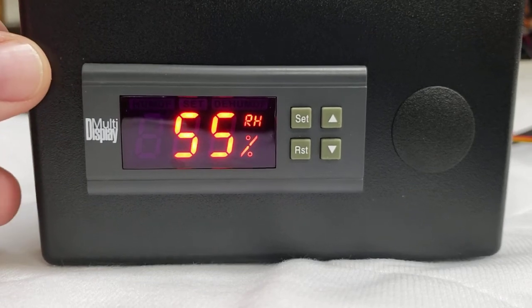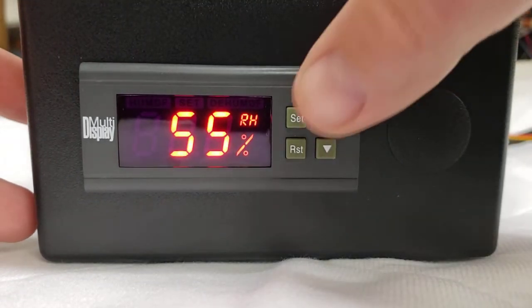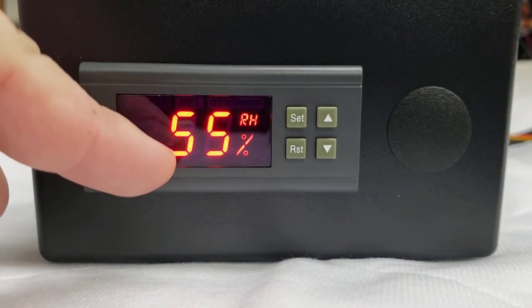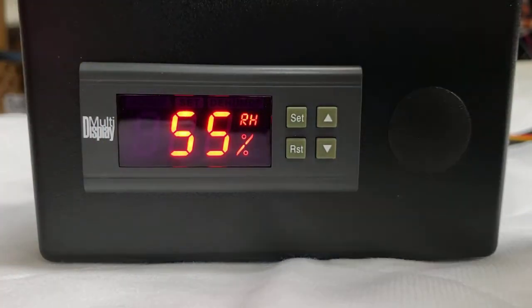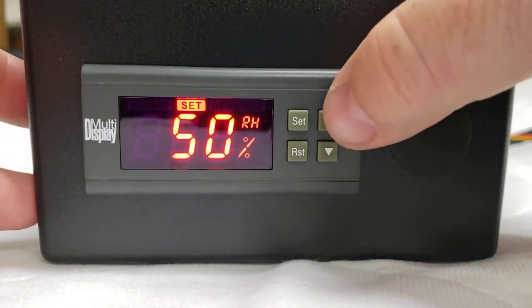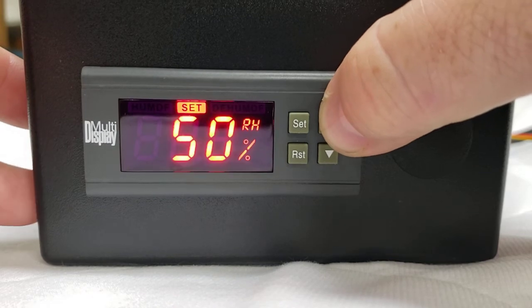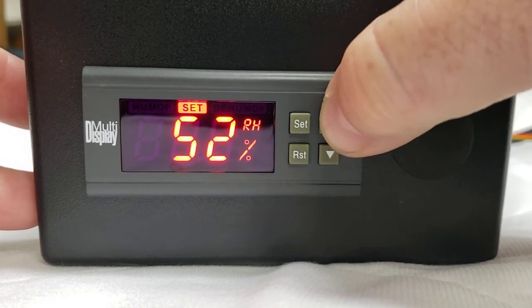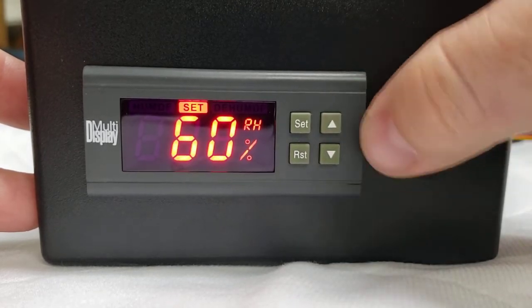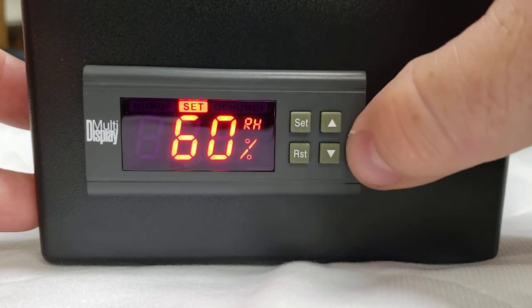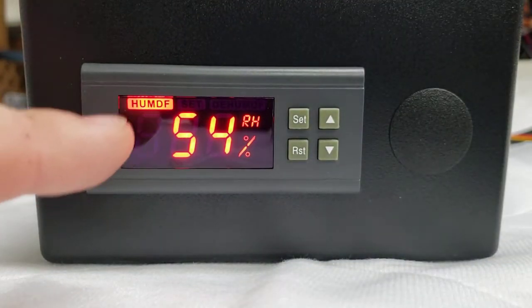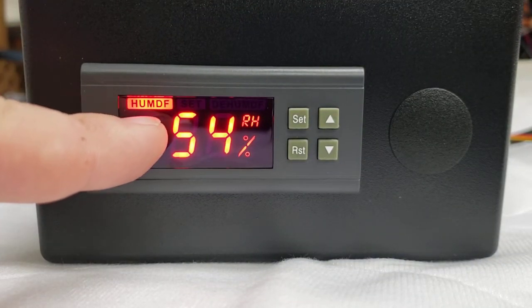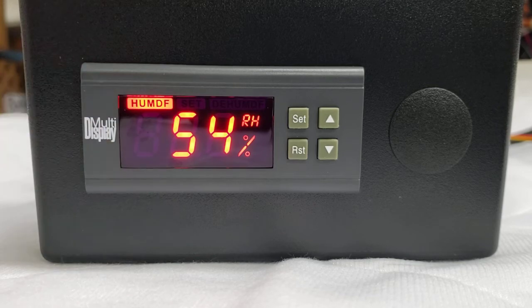Now, if you just need to raise and lower the humidity on the unit, meaning the setting for what you want the humidity level to be in the incubator, you're going to push in and release set one time. It's currently set for 50%, and we want that set for 50 in an incubator. If you wanted more humidity, say 60, you'd move the up or down button to get where you need to, in this case up, and then you'd click set again. Now you're going to see it is humidifying, or some of the models will say working, letting you know that it is putting power to your pump, which should be plugged into the green sticker found on the back of the unit. We actually have those labeled.